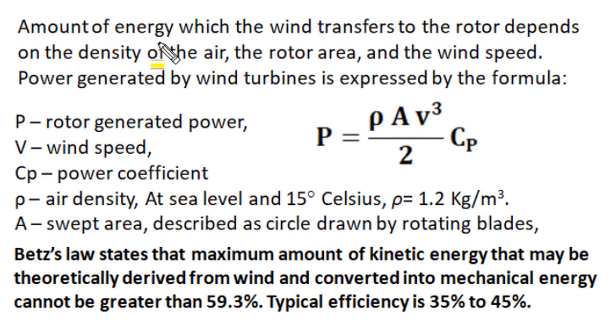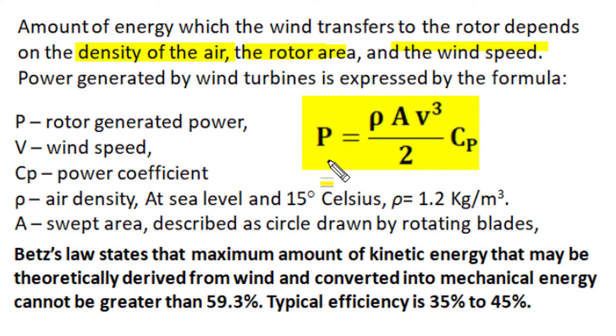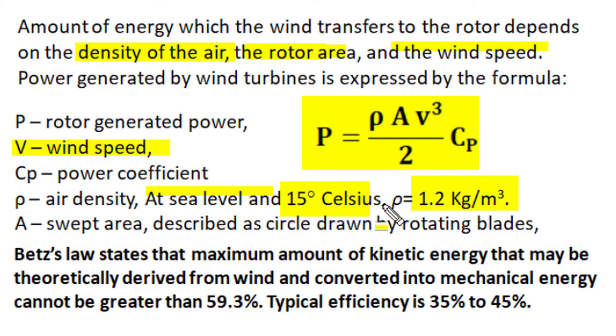The amount of energy which wind transfers to the rotor and produces as electrical energy is directly proportional to the kinetic energy of wind flow across the rotor sweep area. It depends upon the density of air, the sweep area of the rotor blades, and the wind speed. The power generated by a wind turbine is expressed by the relation: P = ½ · ρ · A · V³ · Cp, where P is the rotor-generated mechanical power, ρ is the density of air — approximately 1.2 kg/m³ at 15°C near sea level.